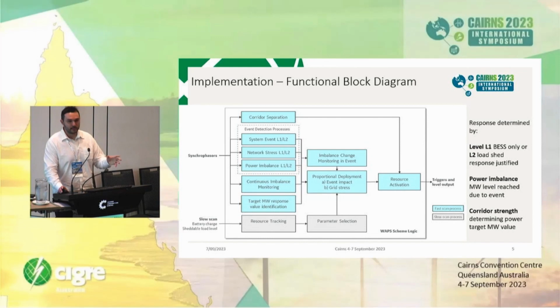And the response is either level 1 or level 2, level 1 being a BESS discharge only, so there's a BESS array that's built, there's a BESS stack, and then for more severe events where level 2 is justified, then we'll look at load shedding as well.